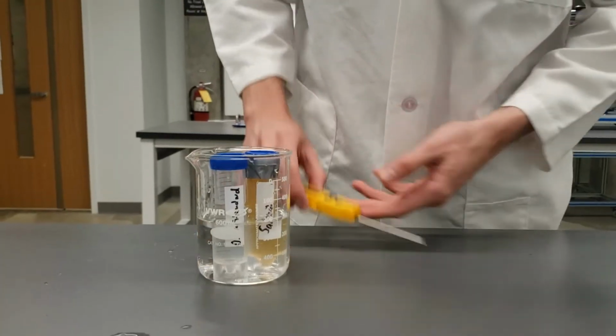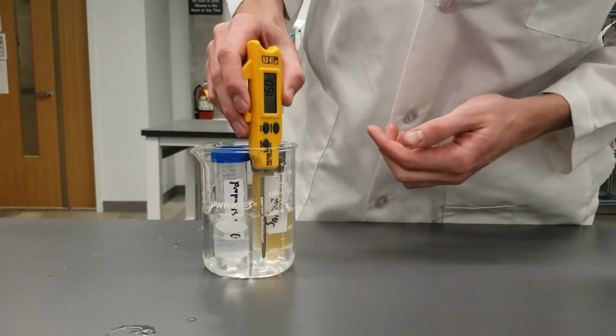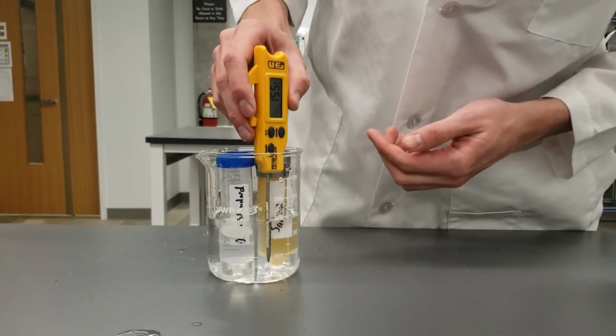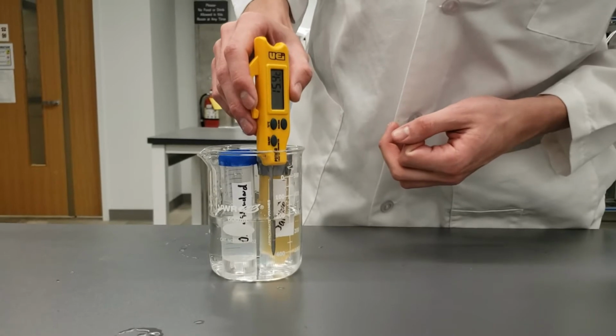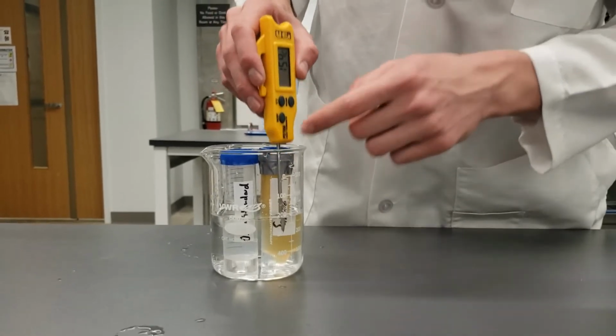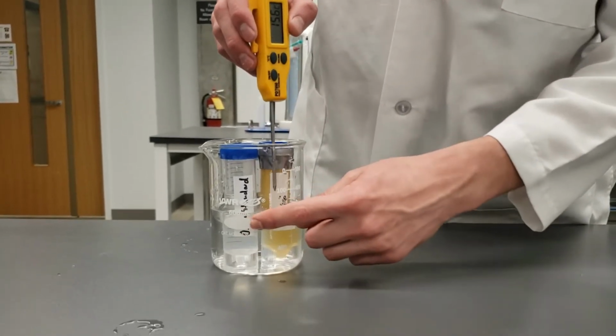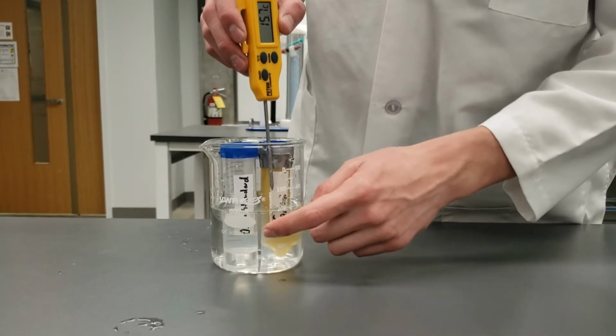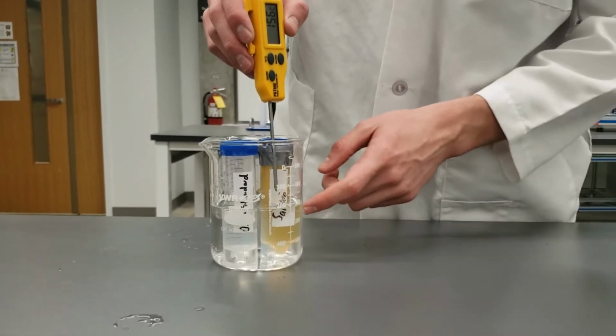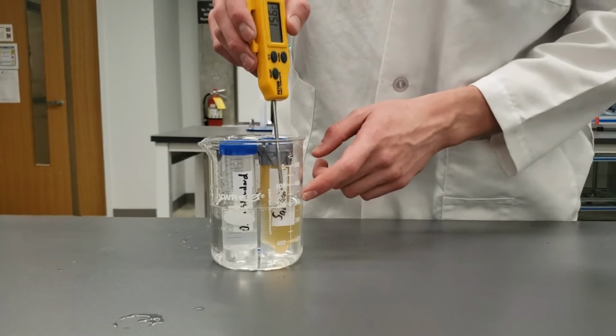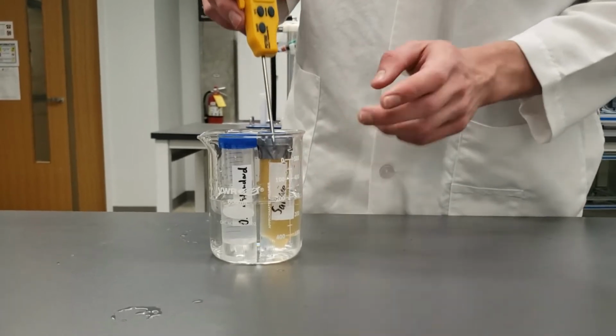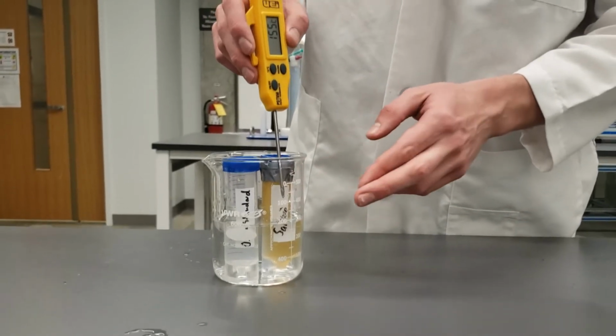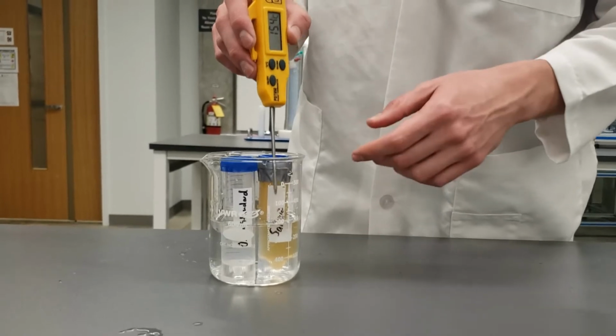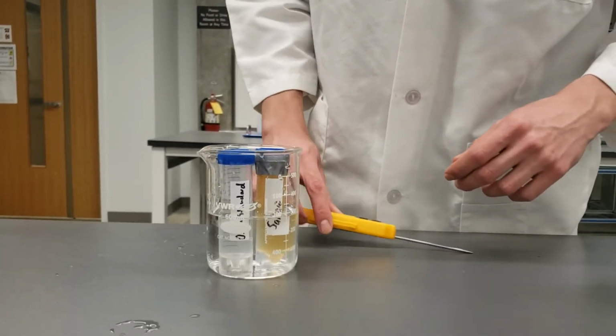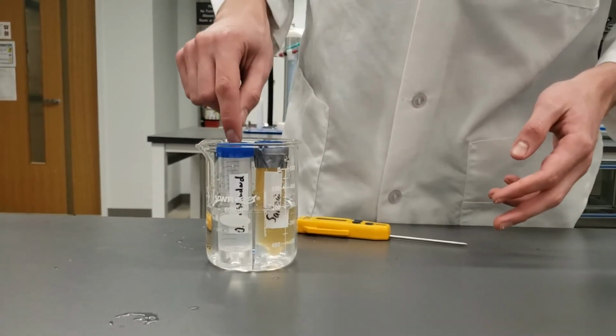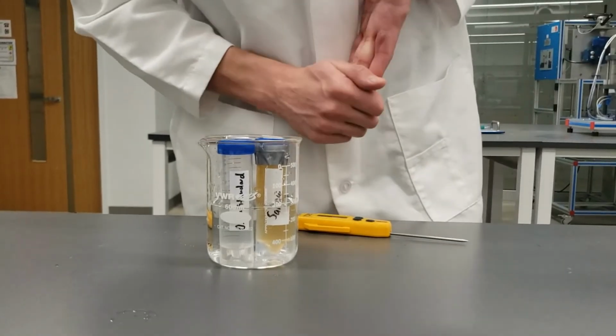Alright, so we're back and we have some slightly cooler water. It's a little less than 16 degrees, closer to 15 degrees C. And you can see we have our 0.5% alcohol standard cooling down in there. And we also have our sample that we're going to test in here as well. Now if you're testing multiple samples, you'll probably want to have an ice bath or have them cooling in the refrigerator down to your calibration temperature while you're calibrating your detector.